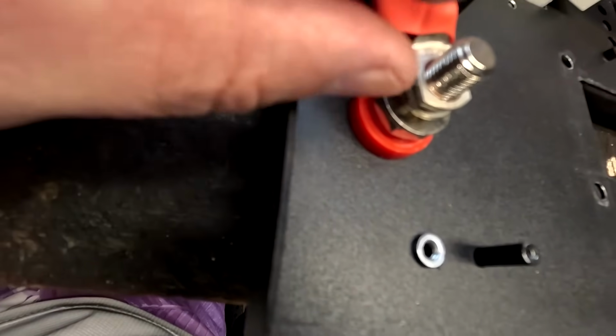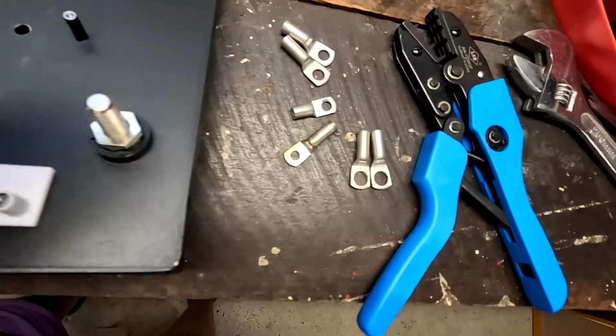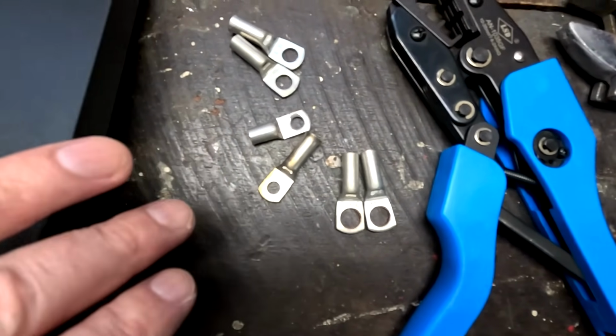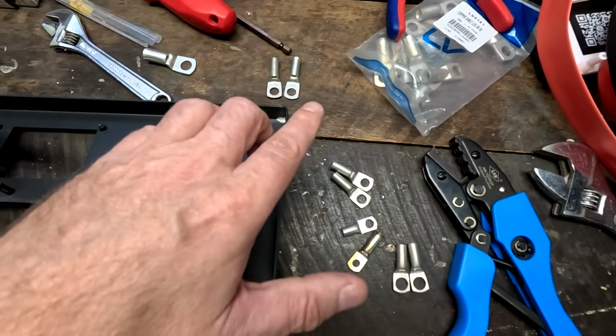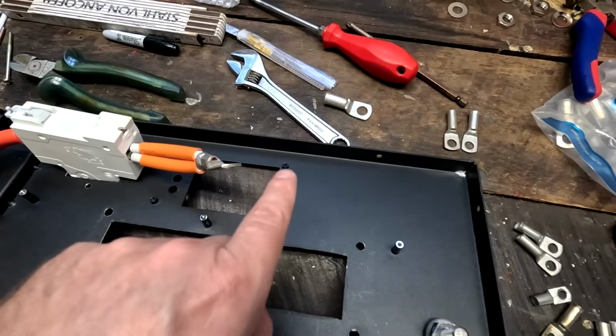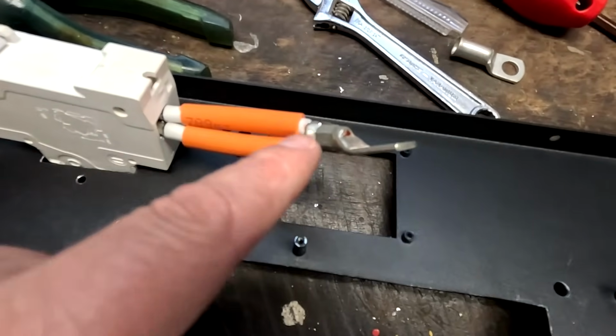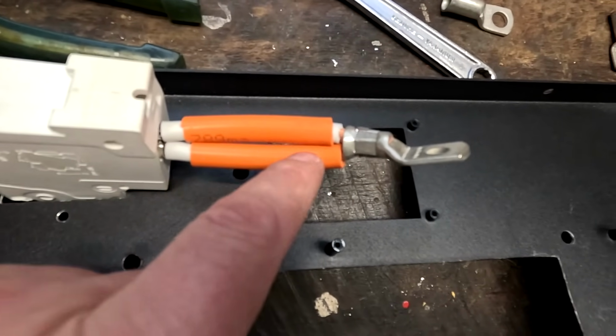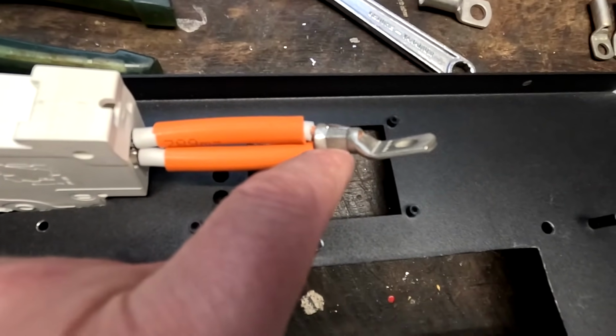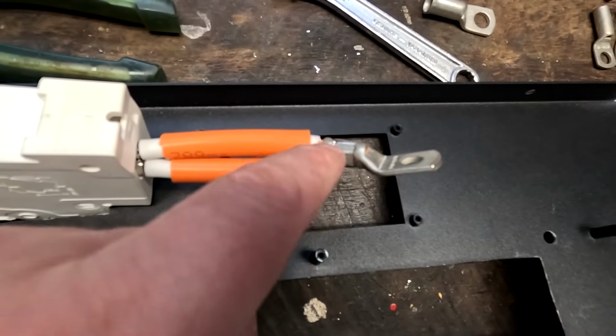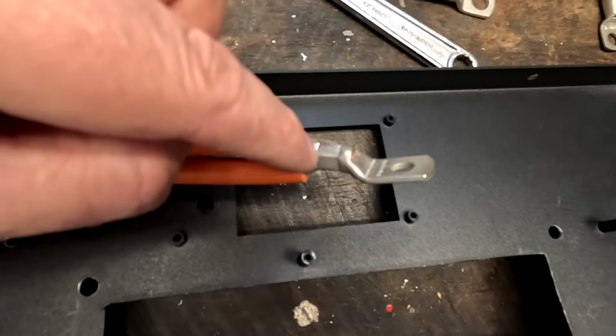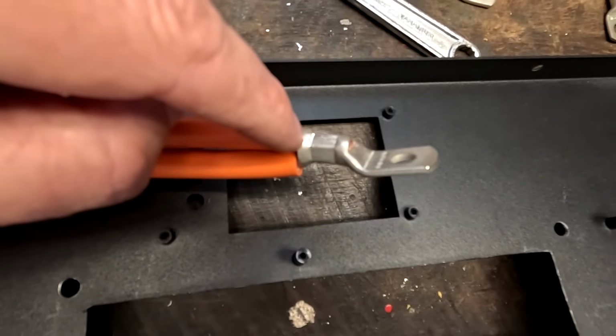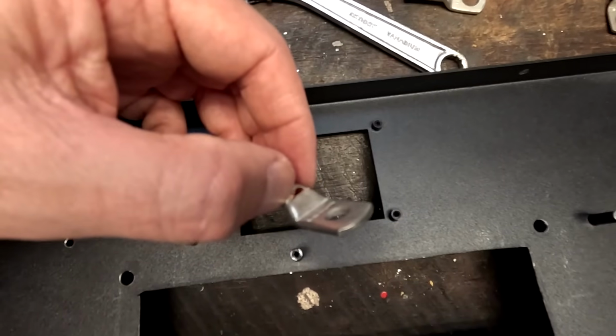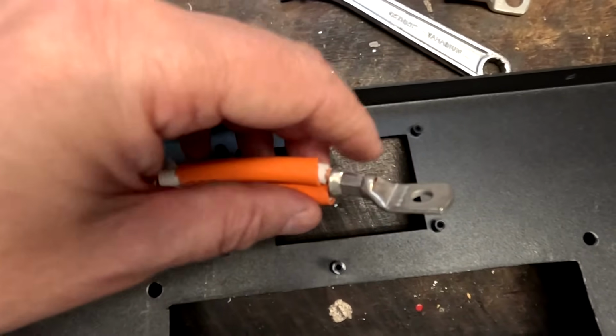As you've seen, I've used 2 separate ring lugs here and put them back to back. But I'm really running out of 16mm ring lugs, and I've got just enough, so this one and the main positive will be a double crimp. Because these are 2 16mm cables and this is a 35mm ring lug, there's some space inside, so I used a 25mm die in the hydraulic crimper. You can see the copper coming out of the window here, and it's rock solid.